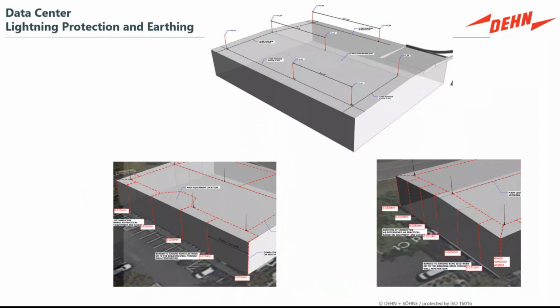These are some great illustrations showing practical applications where portions of the building are already sealed up with concrete, and you can't get to an existing structure. And this is becoming, of course, very common in the industry, to take an existing building and repurpose it as a data center. But what you find is that it's not a perfect world, and maybe the grounding system isn't accessible. Maybe there's a buried ring that you just can't get to. So the lightning protection system has to be adapted with suitable connections and the suitable number and a very clear and distributed route into the soil to reduce the risk of fire and side flash.